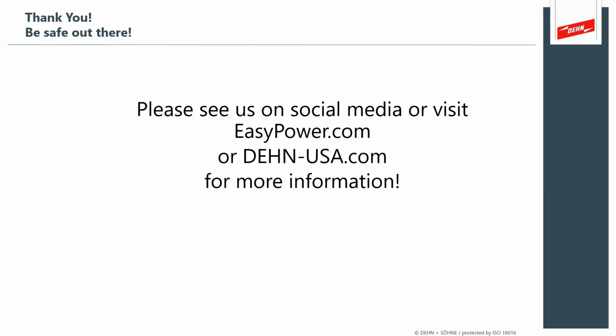Yeah, I get that. The next one is from Aggie Doctor. If the main distribution panel has surge protection, do the downstream panels require it too, or does this just add to the cost of the project? Well, the standards give you a 10-meter suggested, we'll call it grace range, where if you're within the same room that's substantially shielded and you're 10 meters away, you're probably not experiencing much in the way of GPR, ground potential rise. And you're close enough to enjoy the benefit of that SPD.